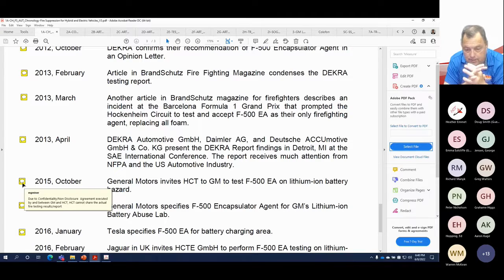And the gentleman that conducted the test is actually on our meeting here. It's one of our firefighters. He used a 20-gallon per minute TKO nozzle, and he had a 2-liter bottle of F500. He was flowing at 3%, and then within 1 minute, everything was extinguished and cooled. He stopped the nozzle, unscrewed the bottle of agent because the 2 liters were gone, and he screwed another bottle in while we were talking with the General Motors people and the fire protection engineer, but never had to use any of the 2nd liter. The fire was out, the temperature was down, and it never rose again.